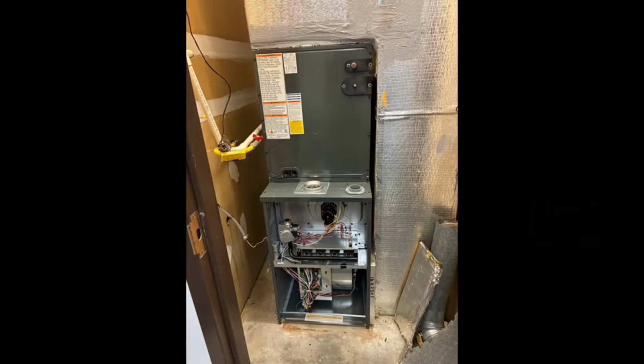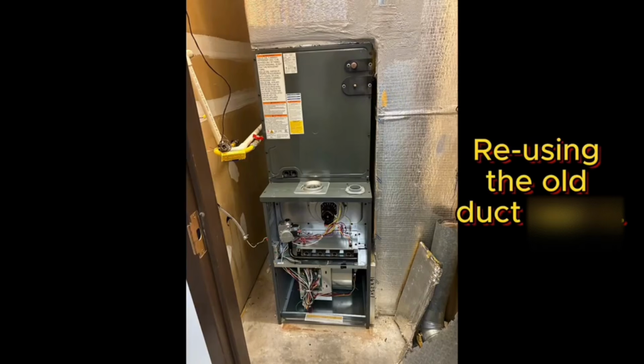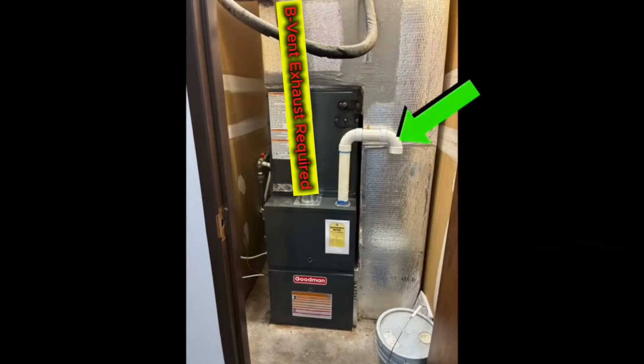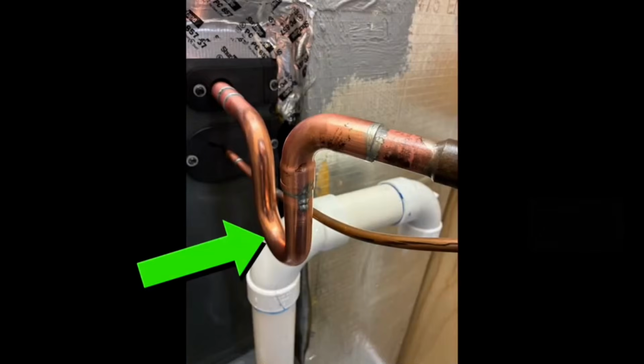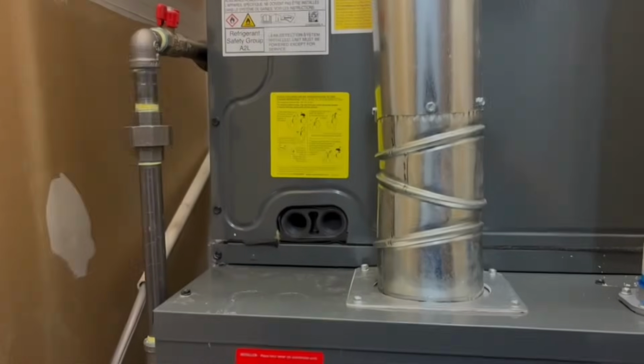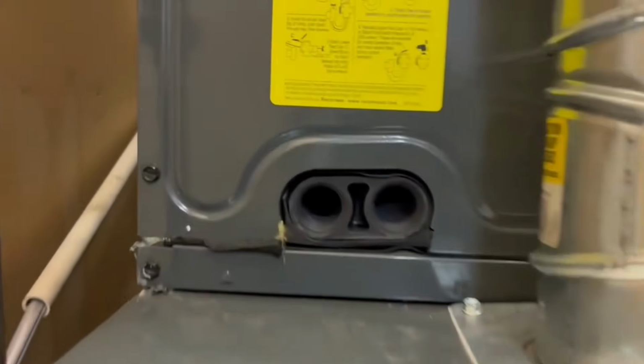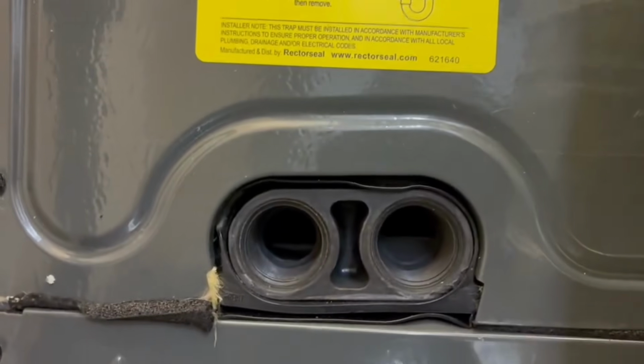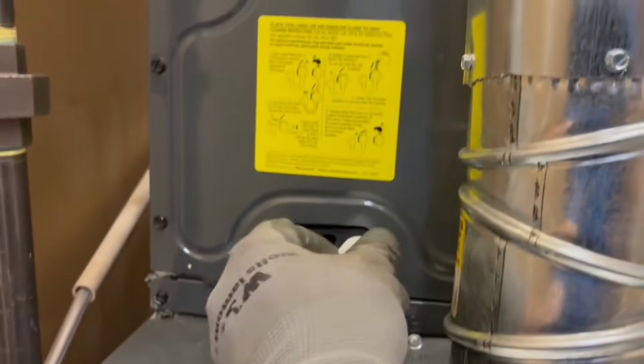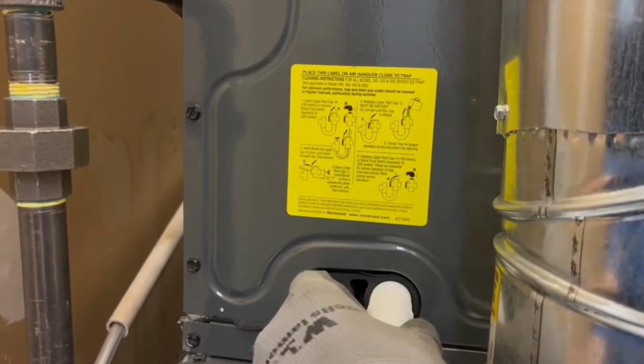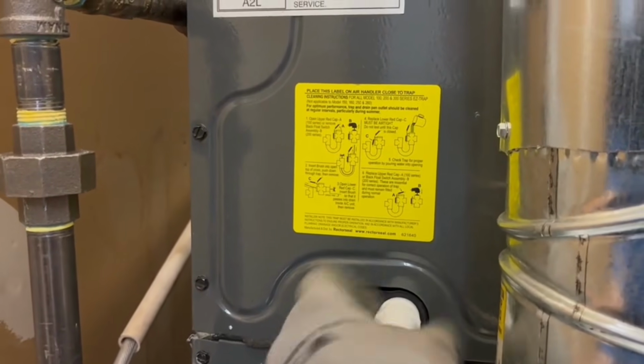So we got the unit placed. You've got our PVC fresh air intake, our exhaust hooked up to the old exhaust, our gas line in place, thermostat wire. This is an oil trap on the suction line. And the oil trap is a place to collect the oil so you don't flood the evaporator with oil when the condensing unit shuts off. So here they require us to do a safety switch on the evaporator drain pan. So if the evaporator fills up with water because the P-trap gets clogged, it'll shut the AC unit off.